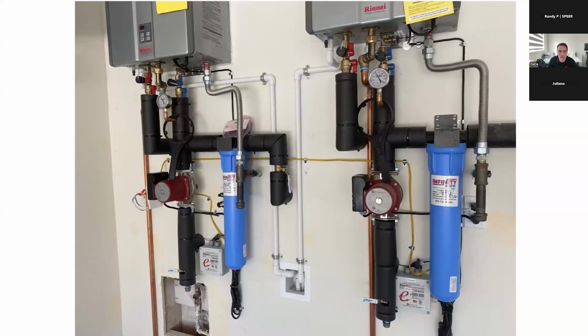Another picture of some return lines with pumps, controls, where you have a bigger home that actually splits the loop into zones. So if it's possible, you want to minimize the circ loop. If the loop is too big, then you may want to consider dividing it into zones.